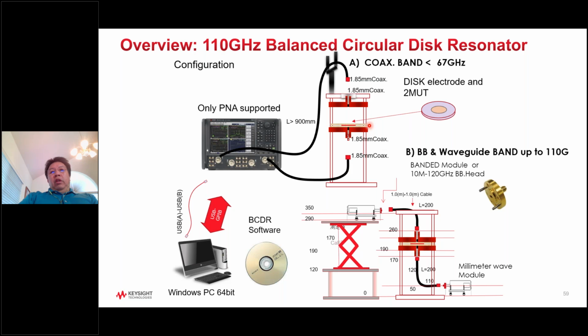So for example, if resonant at, let's say, 17 gigahertz, the next frequency point would be 34 gigahertz, and so on and so forth. And then for the 110 gigahertz, of course, using the millimeter wave, it comes with a little jack here. So that way you can jack up your sample, so you don't bend the cable, and you need to keep the cable really short because at high frequency, your RF loss in the cable is significant. And then the bottom module is shown here.